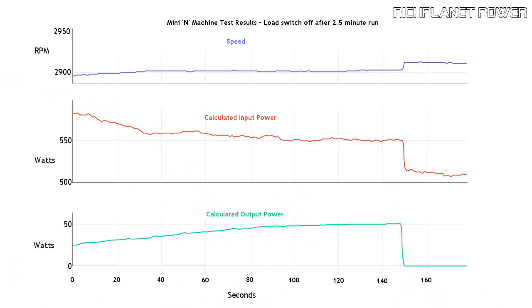So if I ran a motor at twice the speed of the current one, the output current would double from 105 amps to 210 amps, which means the output power would increase by a factor of 4. But hopefully it would only double the increase in input power. Maybe, not sure. So this then may show a much larger than 33% difference between the incremental input and output power. If the input power doubled and the output power quadrupled, would the figure be 206% as I've calculated? I don't know. So if it could get up to 200%, that would be a lot more convincing than the 133% that it currently is.